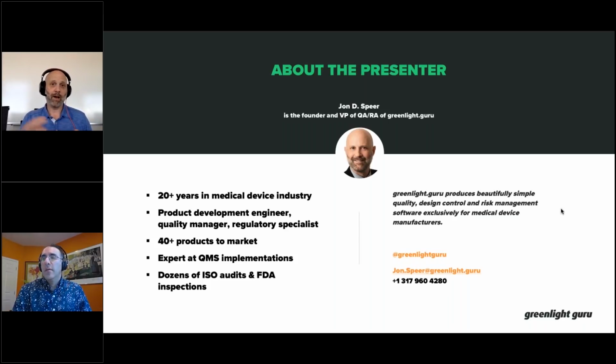It's going to drive decisions to make sure that I'm designing, developing, and manufacturing the best possible product to mitigate, reduce, and control risk as it relates to that patient and end user. So it might drive activities from a design and development process. It might drive activities from a business perspective. It might drive user training programs. There's a lot of different possibilities. So that's the way I think of it. I want to be more holistic, more patient-centered in my risk management efforts.